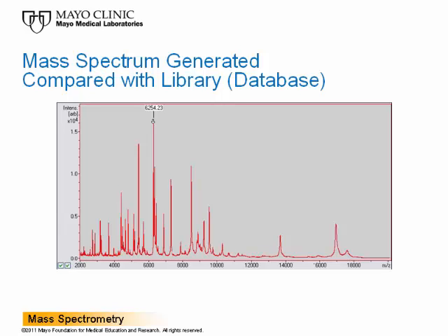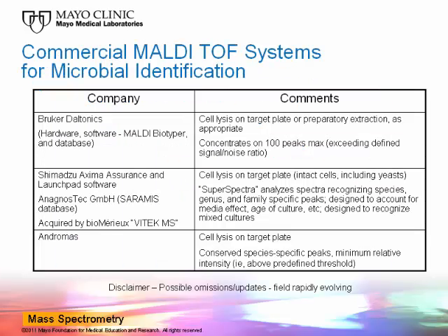The spectrum typically includes genus and species-specific peaks, so that with a comprehensive library of spectra, the genus and often the species of the organism may be determined using bioinformatics. Multiple commercial platforms are available. The most studied system is from Bruker Daltonics and includes a mass spectrometer along with the Biotyper software and database. Another system uses a Shimadzu mass spectrometer with Launchpad software and the Anagnostec GmbH Saramis database, recently acquired by bioMérieux and being redeveloped as Vitek MS. Yet another system, Andromas, is used mostly in Europe.